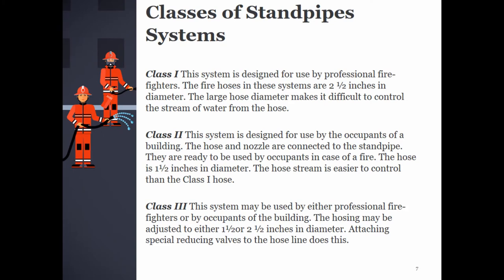Classes of Standpipe Systems: Standpipe systems are classified depending on who is expected to use them. Class 1 is designed for use by professional firefighters; fire hoses are 2½ inches in diameter, making the stream difficult to control. Class 2 is designed for use by building occupants; the hose and nozzle are ready for use and the hose is 1½ inches in diameter, with a stream easier to control. Class 3 may be used by either professional firefighters or occupants; the hose may be adjusted to either 1½ or 2½ inches in diameter by attaching special reducing valves.